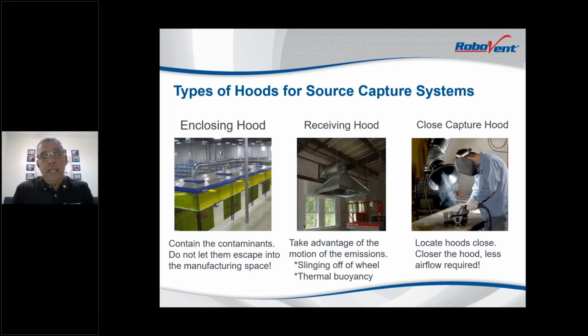The next type is a receiving hood, and that is using the momentum of the particulate generation. The way to think of it would be like a catcher's mitt. If you have a grinding operation, for instance, and there's not an enclosure around it, that grinding wheel is going to throw the particulate. The lathe is going to throw the particulate in one unique pattern. Well, use that pattern as the location of your receiving hood, and then duct it to your filter.